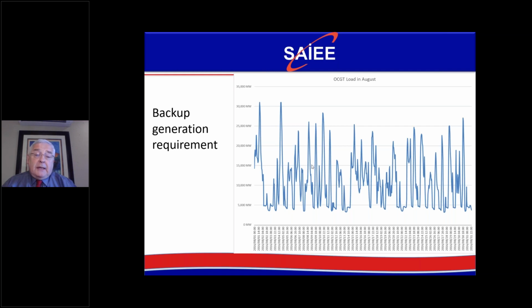What's interesting to say is that although you've got a model, and I'll show you in a second the numbers, where you've got an enormous amount, way more than installed capacity, way more than demand, this is what the backup generation is running. So the gas turbines are running that profile over the month. They peak out at about 32,000 megawatts, minimum about 4,000 megawatts. They never go to zero, because if they go to zero, the grid would become unstable because there'll be no stability. Synchronization wouldn't be maintained on the grid.